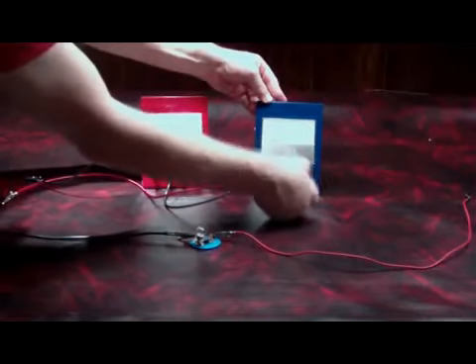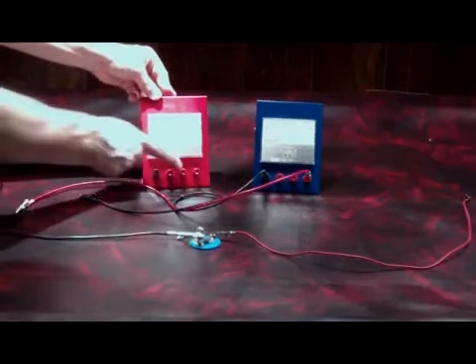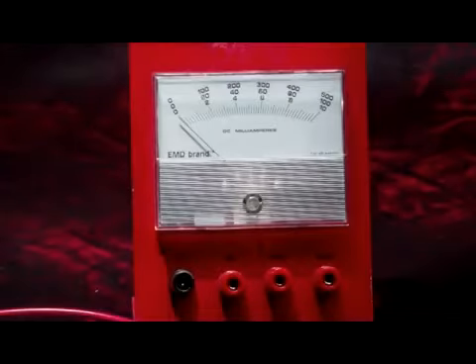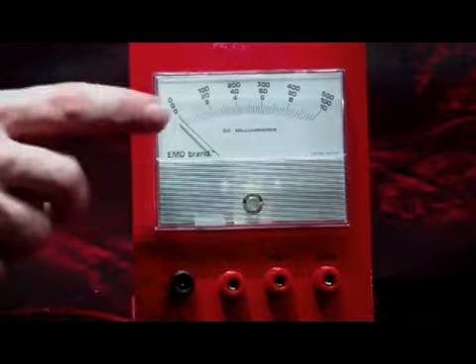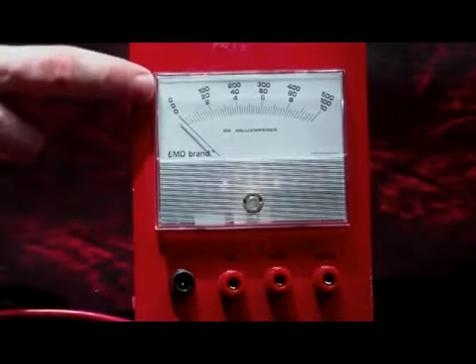Now I've mentioned that there were three different red ports on each meter. Well, these three different ports are a low, a medium, and a high. Depending on the sensitivity of the meter and what you want, you'll select that particular port. Notice the three ports. The leftmost goes with the bottom set of numbers. The middle goes with the middle set of numbers. And the rightmost goes with the top set of numbers.